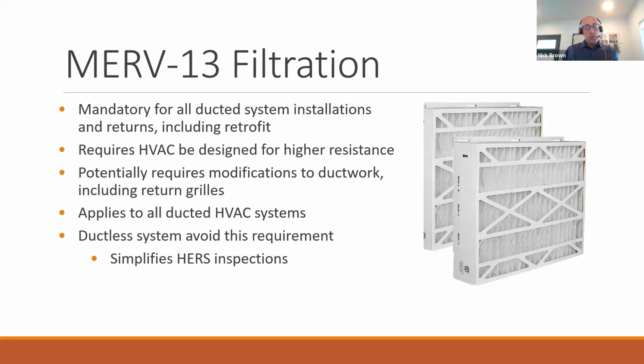One other requirement that I want to make sure you're aware of, it's been in the code since 2020, so 4 years already: your return filter grills need to be equipped with MERV 13 filters. And these typically look like what's pictured here, either 4-inch or 2-inch deep filters, not the 1-inch units that I was used to before this code change. So that means higher resistance on your air handling fan. It means that your system needs to be designed from the start to have this much resistance, not just the filter grill accommodating this thickness of filter, but everything designed with this amount of pressure drop in mind. So there's another reason you're going to have to put in a MERV 13 return filter with your retrofit.